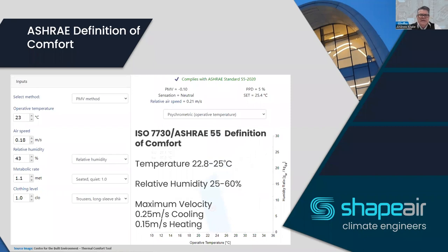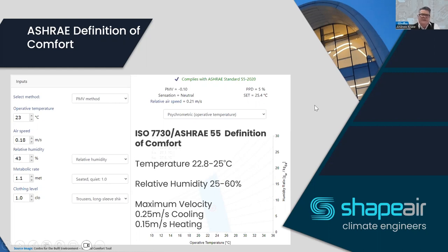The ASHRAE definition of comfort specifies temperature 22.8 to 25°C, relative humidity 25 to 60%, with a maximum velocity of 0.25 m/s in cooling and 0.15 m/s in heating. Remember these values — the airspeed of 0.18 m/s used here and the 0.25 m/s limit will come up again in the presentation.